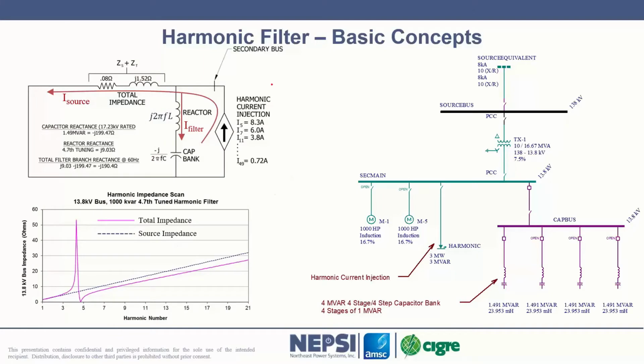If I go from looking at the 2 impedance values and then instead look at, well, what is the impedance if I look into the circuit from here, I get this magenta curve, the total impedance curve. And obviously, the reason why filters work is that they look to minimize the impedance of this network. We have a source impedance in parallel with another impedance. And of course, along that whole distance here, we have less impedance and therefore less voltage distortion because we're pulling in current here and it's going through less impedance.